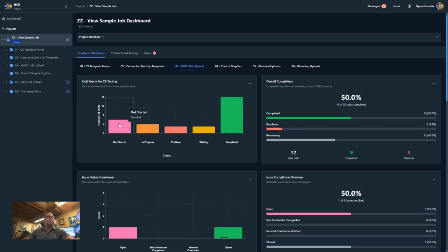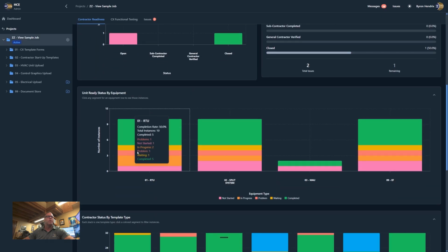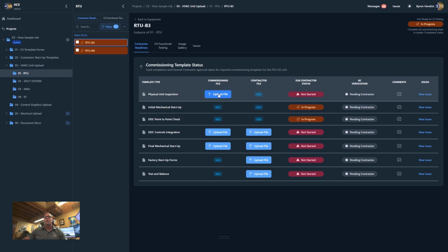Now, I was telling you that these are clickable. So one of the things we can do, let's dial in on the rooftops. So in the rooftops, we can see we've got all statuses here, but I want to see the ones that are in progress. Okay, just these two are in progress. Well, let's go see what's going on with these two. Okay, so they've done the initial startup and the DDC point to point check, but nothing else has been done.